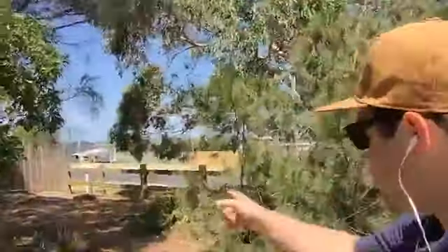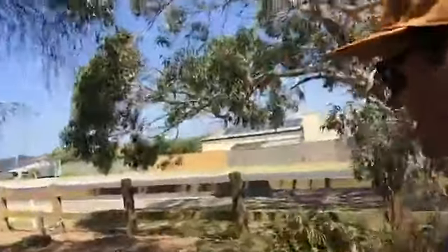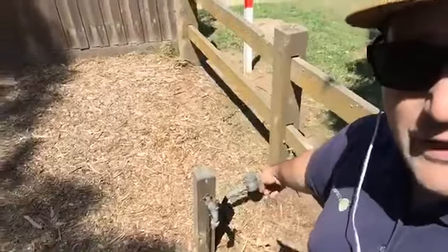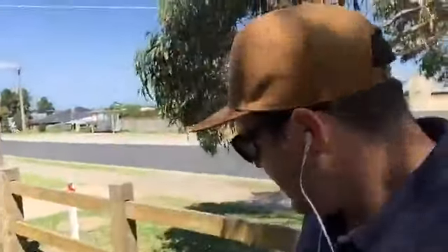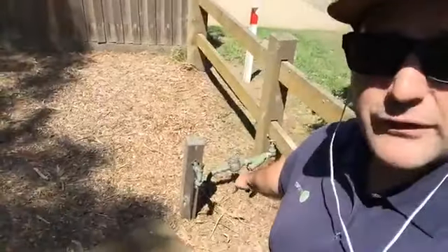So what I wanted to do is show you how we'd tackle that. Let's say it's a standard drip line off a standard drinking water supply, standard water meter. There's essentially two types of backflow devices that we have to put in there. Just over here, we have a water meter, and that's the water meter that feeds this park. In most situations in a park this size, that water meter will be way too small, but don't worry about the flow or the size. Essentially that doesn't have a backflow device on it.